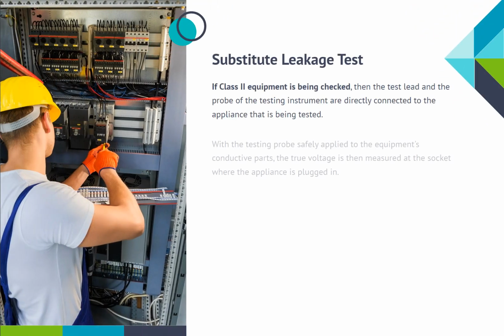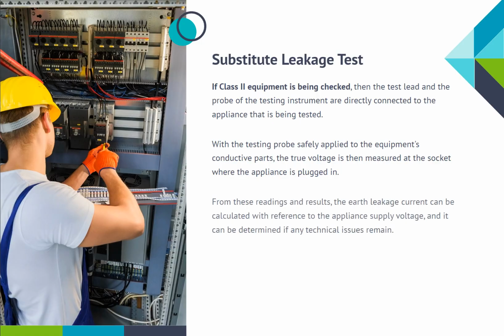If Class II equipment is being checked, then the test lead and the probe of the testing instrument are directly connected to the appliance that is being tested. With the testing probes safely applied to the equipment's conductive parts, the true voltage is then measured at the socket where the appliance is plugged in. From these readings and results, the earth leakage current can be calculated with reference to the appliance supply voltage, and it can be determined if any technical issues remain.